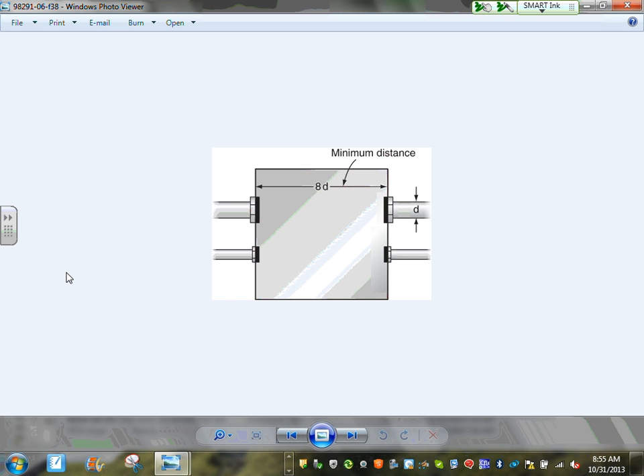Let me summarize the box fill calculation with two things. If you have a conductor, really all that you have to do is, let's just write the section first. It's 314.28, from 314.28(A)(1). Everything that I'm going to say here, guys, is coming from 314.28(A)(1). And so that's the article.